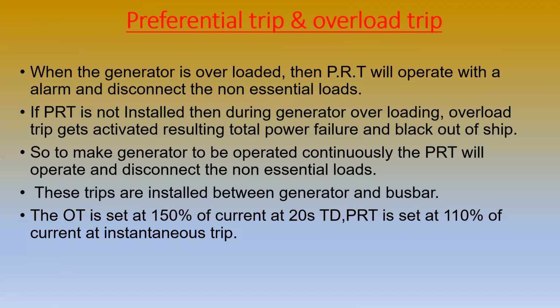The overload trip is set at 150% of the current, and that trip will operate after a 20 second time delay. The time delay is kept because sometimes there may be a sudden surge of voltage, and that may be all right within some seconds. We do not know what the exact condition is, so it may last for some seconds and be all right. So a time delay is kept, and a dashpot is connected.